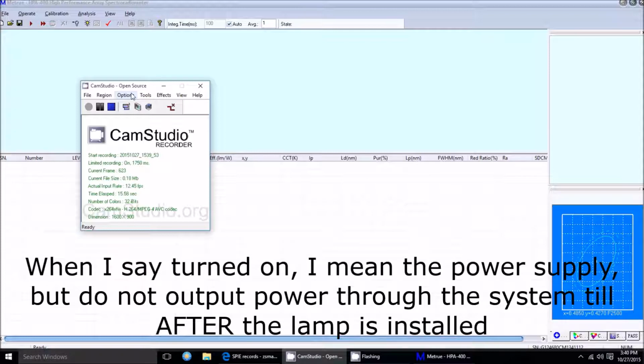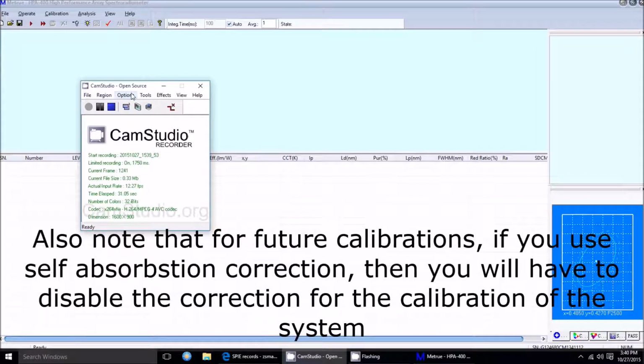I would like to note now that the DC power supply should be turned on before you mount the lamp, because when you turn it on, there is the potential for it to send a surge through, and the lamp is fairly fragile. And for the lamp to keep its own calibration, it's important to keep any such surges from hitting it. So in most cases it would be fine, but just to be safe, always turn on the power supply before you connect the lamp.